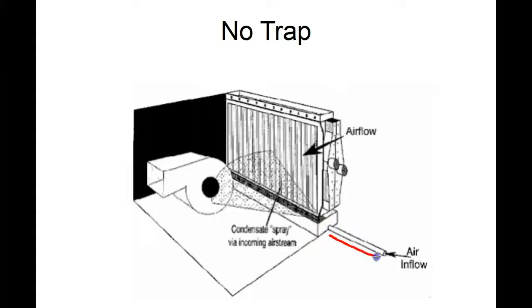If we just have a straight pipe with a nice quarter inch per foot of drop and we're running the air conditioning, this blower creates a negative air flow that starts to pull the air from the outside through this pipe and into the air handler itself. What happens is that it has such force that the water won't drain out. Then the water starts to fill up the drain pan at the bottom.